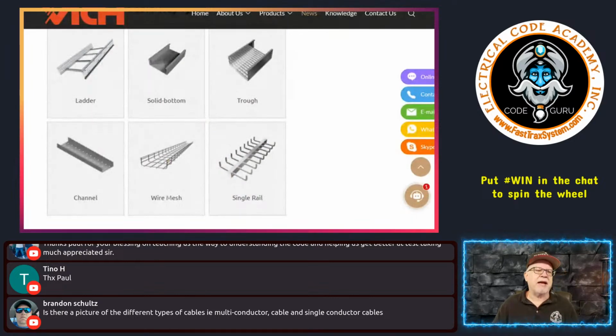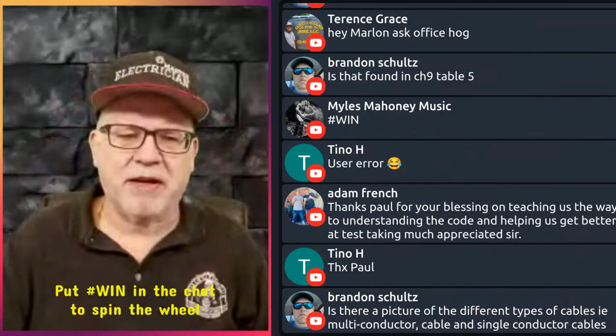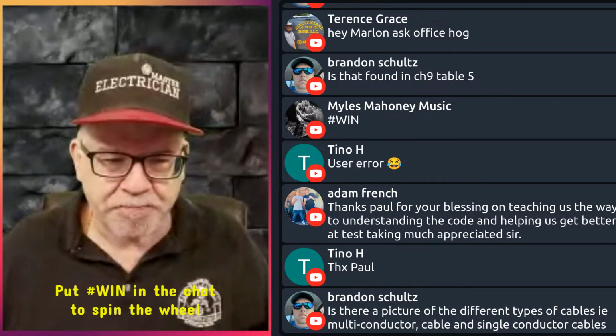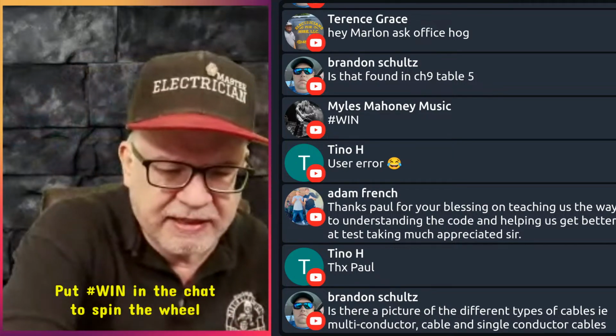Also, do not discount the manufacturers. Always reach out. And also NEMA, by the way. NEMA has a great document out. You just search for it. Search for NEMA cable tray. It may be older by now. I don't know if they put out a new one, but it's still applicable. It still works. NEMA's cable tray installation guide. Go Google search that. And that has a step-by-step guide that is really good too. The reason it hasn't been updated is probably because it doesn't need to be, except that if some of the code references have changed, that might throw off some people. Okay? All right. That's the basics. I don't want to get too deep than that. That's basically your ampacity values.